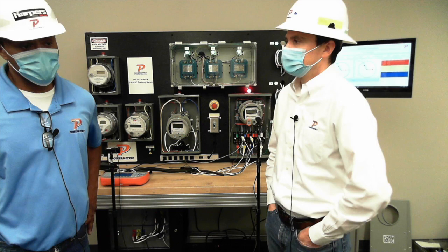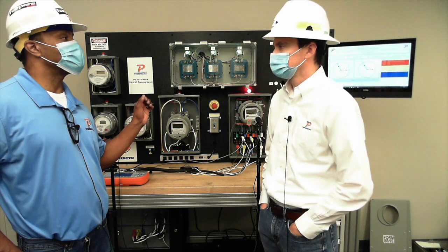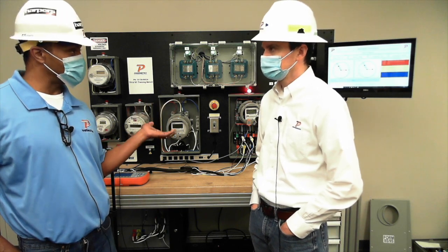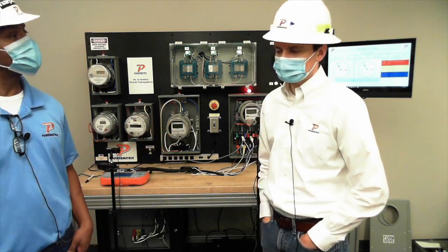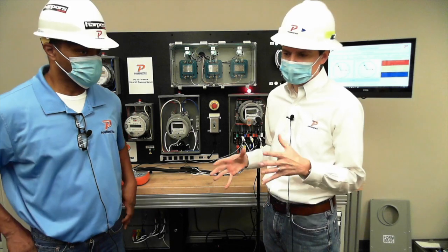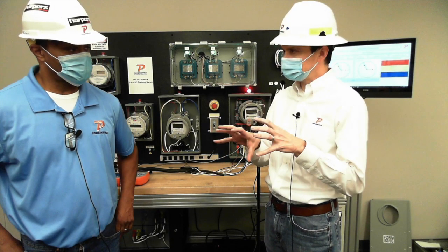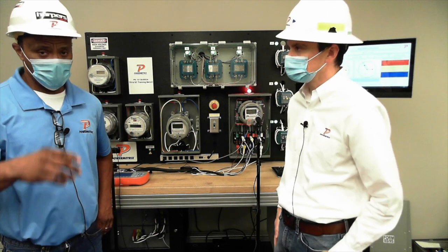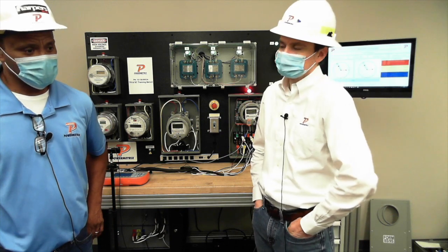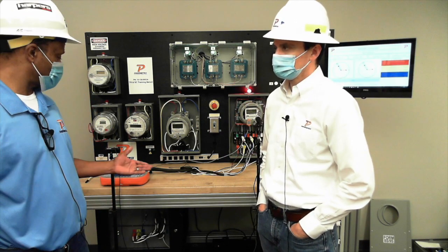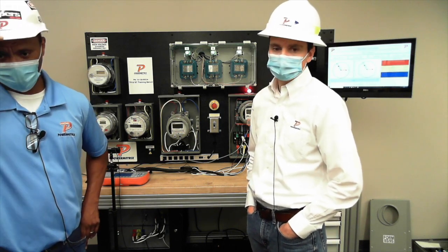You have to do it a little differently. You have to actually reset the meter on the 4 Series. Once you reset it, you hit start at the same time, you press them both at the same time, and then it accumulates, and then you write down the ending number. For those who don't know, the 4 Series has a ZIF socket where you can plug the meter in and just run a phantom load test only. There are no CTs, no connections, right? But it's good too. So you get the same thing with it as what you're seeing here.